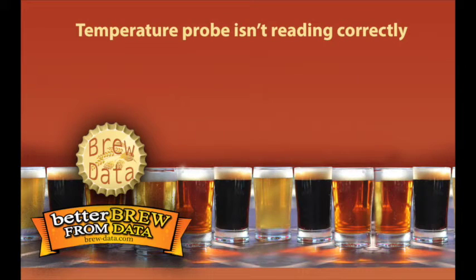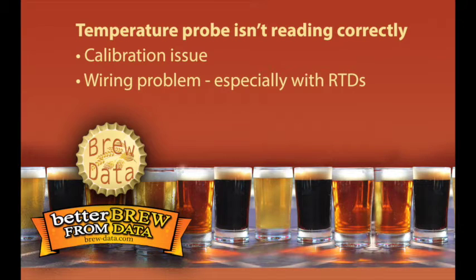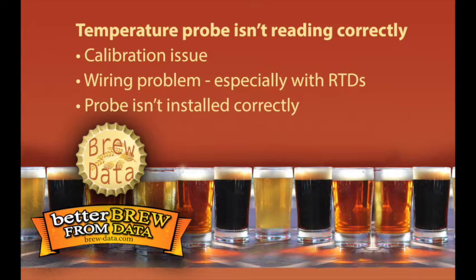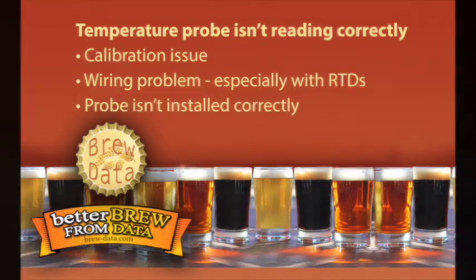A common complaint that I hear from brewers is that one of their temperature probes isn't reading the correct temperature. This might be due to a calibration issue or a wiring problem, especially for RTDs. The most common reason that I've seen is that the temperature probe is not installed correctly inside of the thermowell.